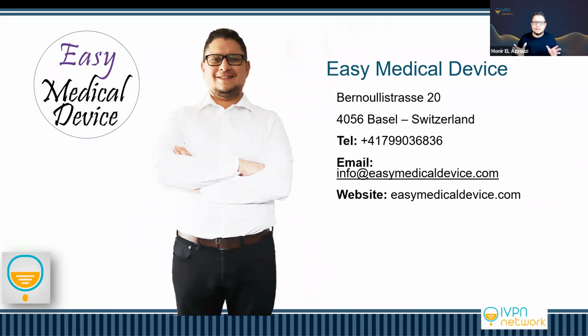So normally, when you have software that is embedded, meaning it's inside the medical device, yes, because as you said, it's a system, but you still have to classify each element one by one. If the software is included inside and is driving the device, yes, this will also drive the classification.